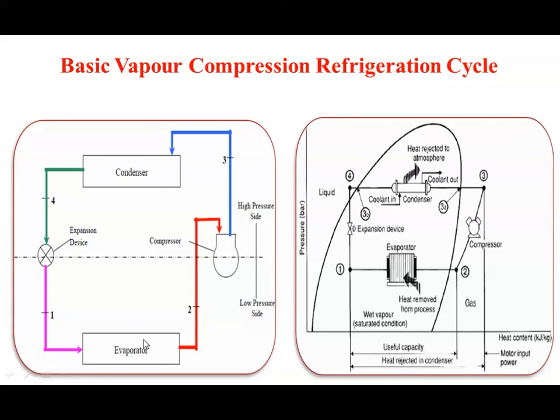This VCR system is generally called a latent heat pump — we extract the latent heat of evaporation in the evaporator and reject it to the atmosphere as latent heat of condensation in the condenser. On the P-H chart, the cycle is shown as: point 1 to 2 — evaporation process; point 2 to 3 — compression process; point 3 to 4 — condensation process; point 4 to 1 — expansion process.